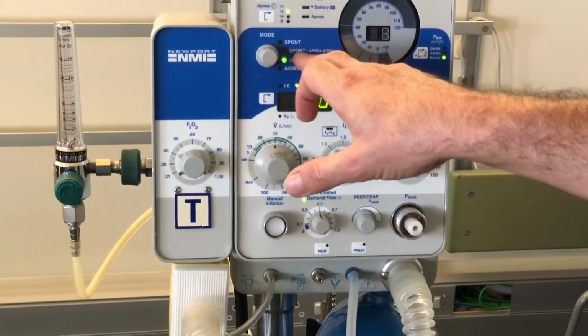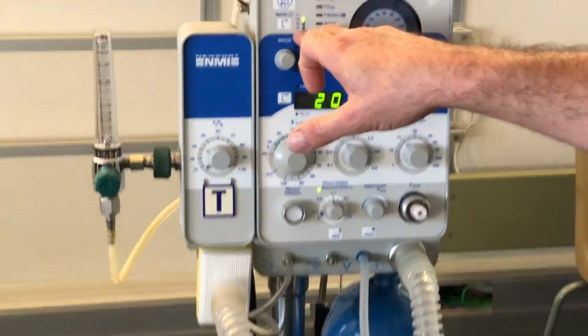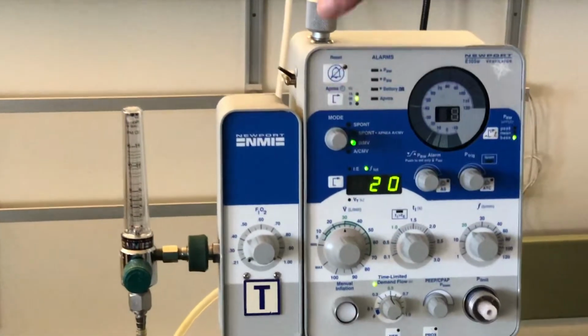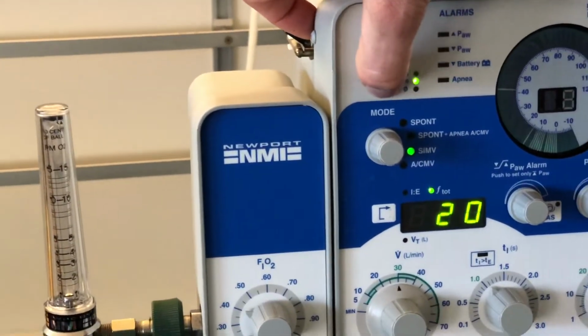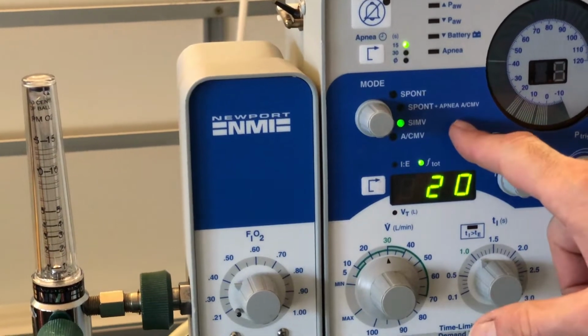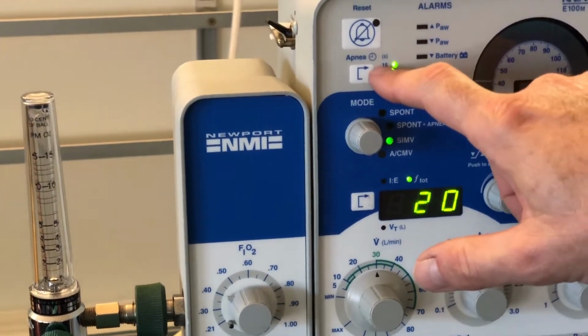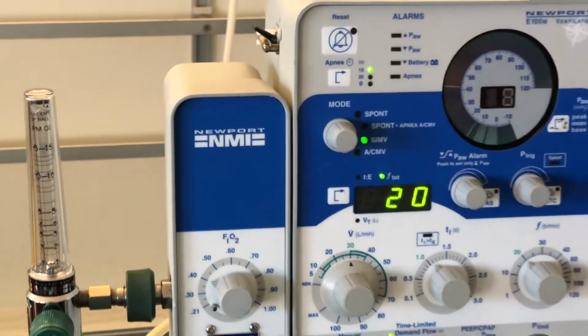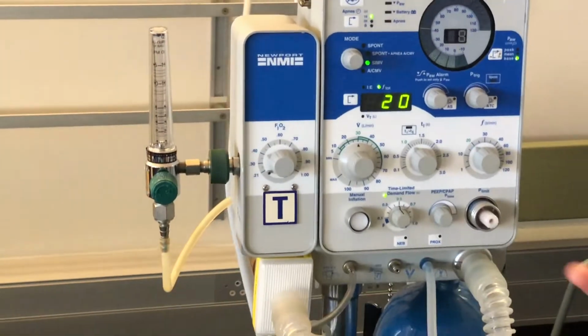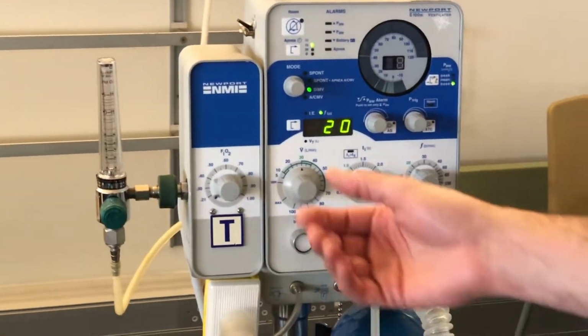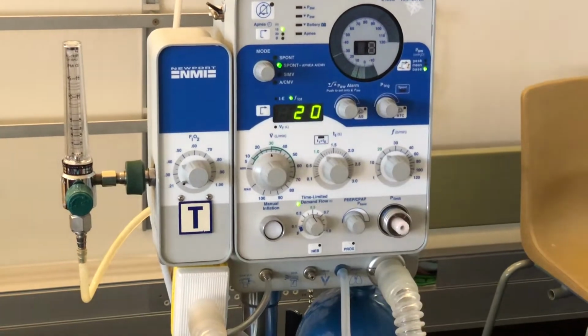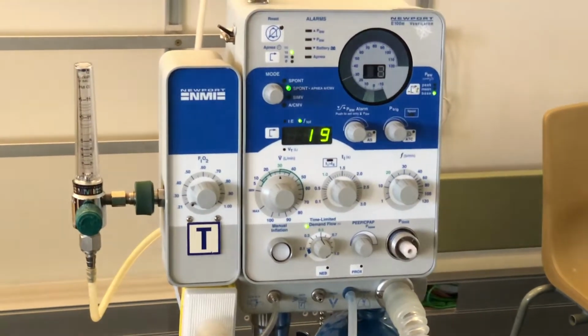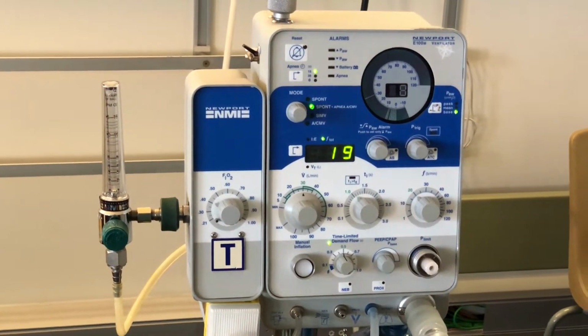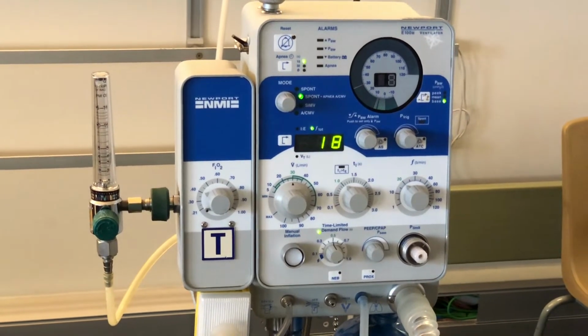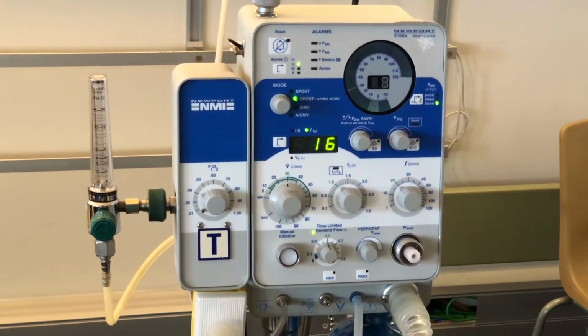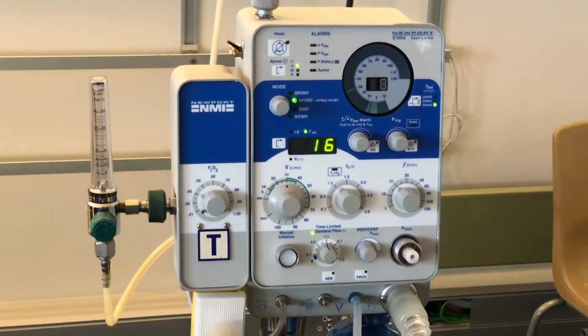And for the spontaneous mode with apnea backup, we can select the amount of seconds that the machine will wait before providing backup ventilation. So at the moment I've set it to wait 15 seconds before the backup mode kicks in. And so what I'm going to do is I'm going to switch the machine into the spontaneous mode, but clearly we're not going to trigger the machine. So after 15 seconds have elapsed, the machine should detect that there's apnea and it should start to provide automatic backup for the patient.